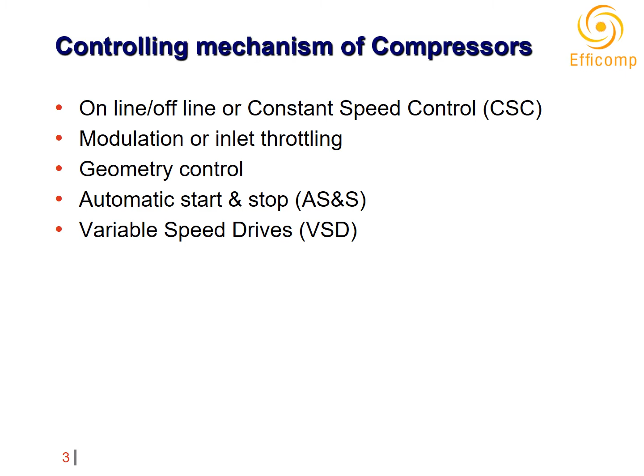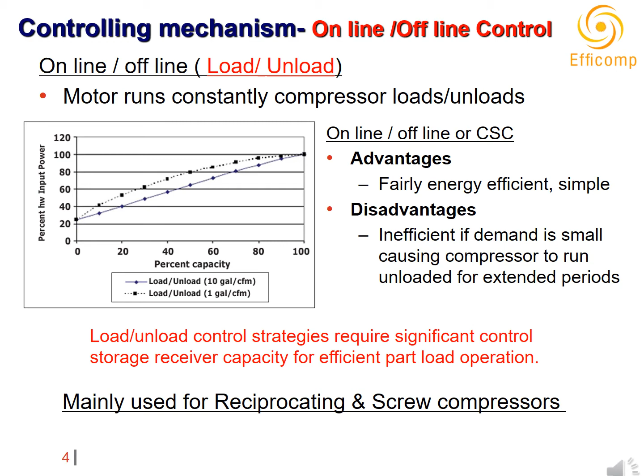Various individual compressor control strategies exist, including the following. This control mode is sometimes called online-offline control. It keeps the motor running continuously but unloads the compressor when the discharge pressure is adequate. Unloaded rotary screw compressors typically consume 15 to 35% of their full load power demand while producing no useful compressed air output. Optional unload timers are available that will save energy by automatically turning off the compressor and placing it in standby if the unit runs unloaded for a period of time, usually 15 minutes. Load-unload control strategies require significant control storage receiver capacity for efficient part load operation.